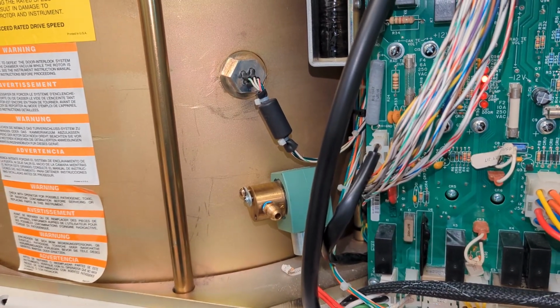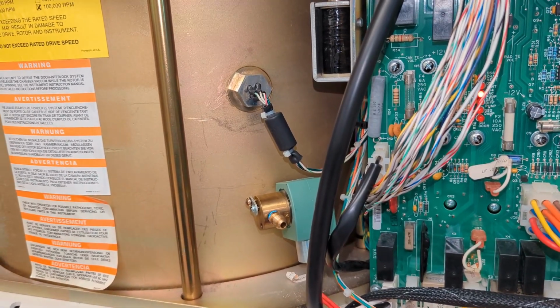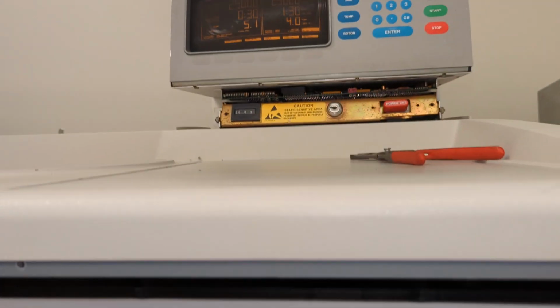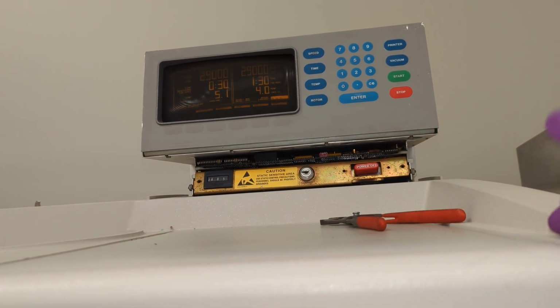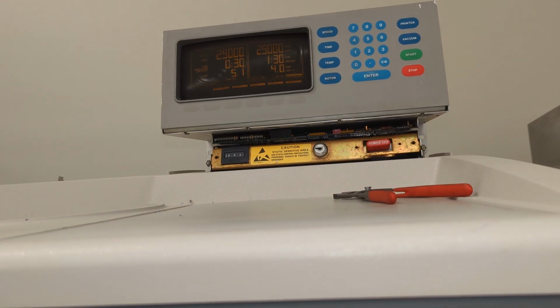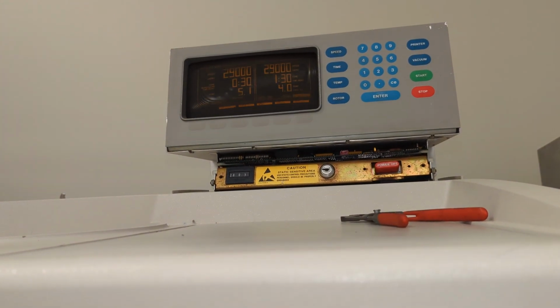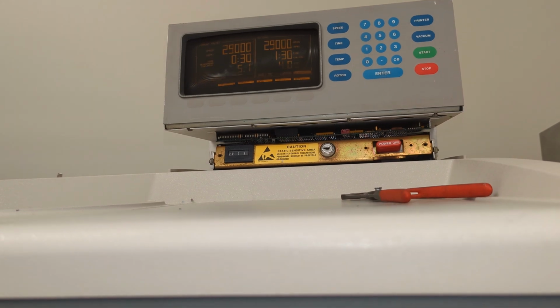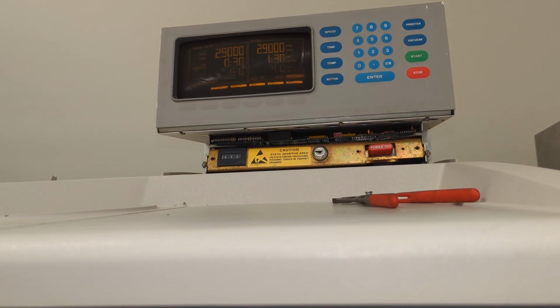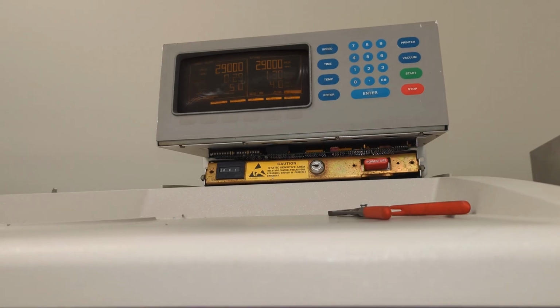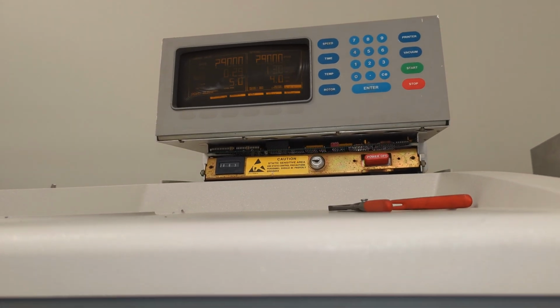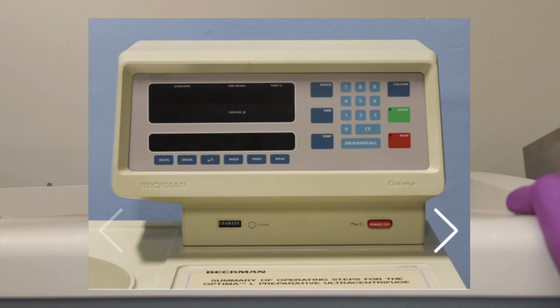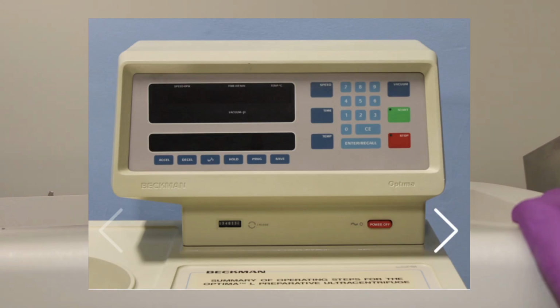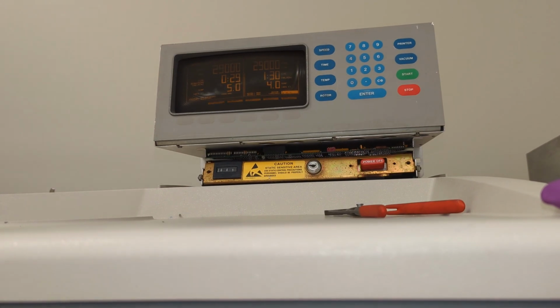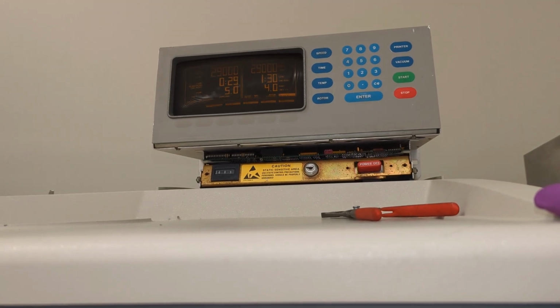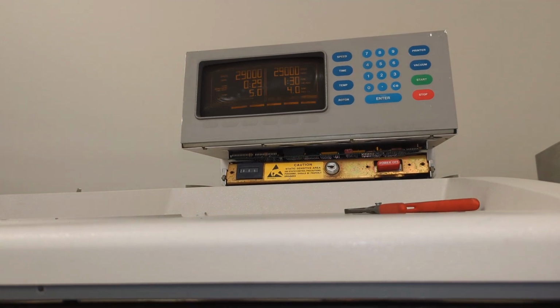The problem with that is, and I may have gone over this earlier in this video, I have no means to calibrate the unit using either this controller or even the XP style controller. Apparently, I've heard from colleagues that you need an L series controller to calibrate these, and those are the ones that just have a 7-segment LED display and the buttons, and you can key in a service code to put it into calibration mode. I've been looking into possibly getting one of those so I can give that a try.